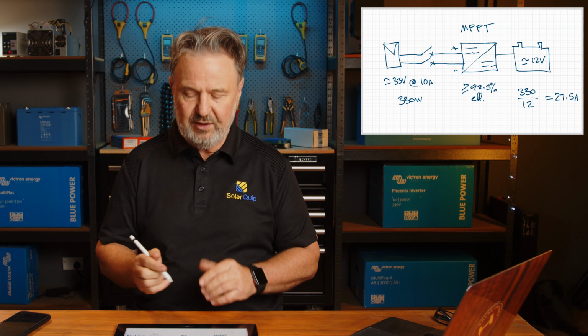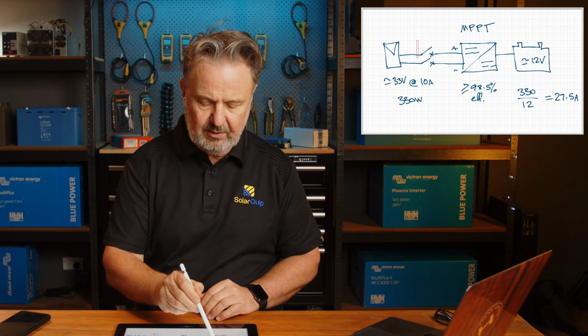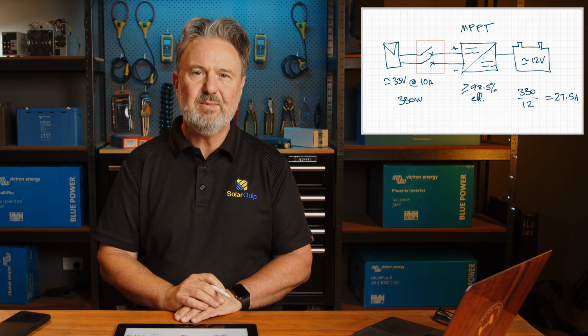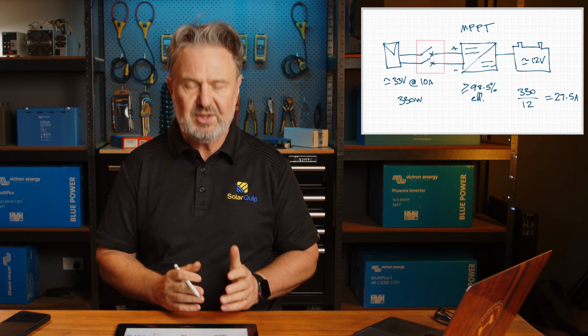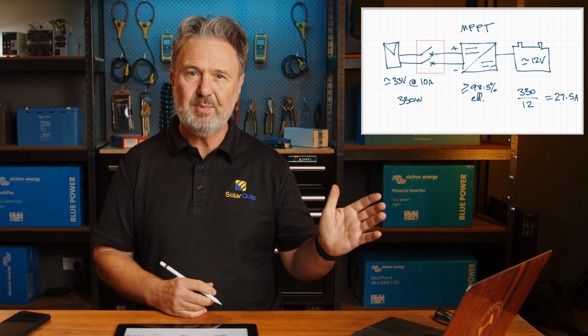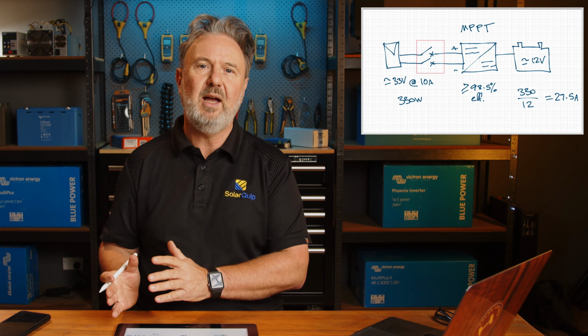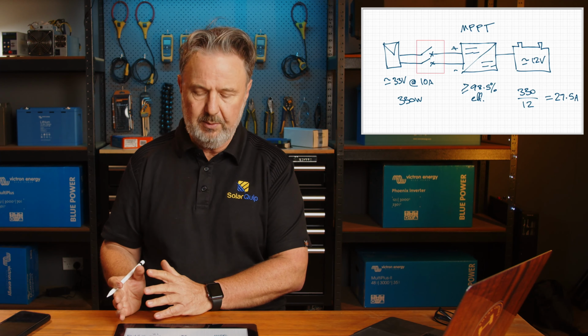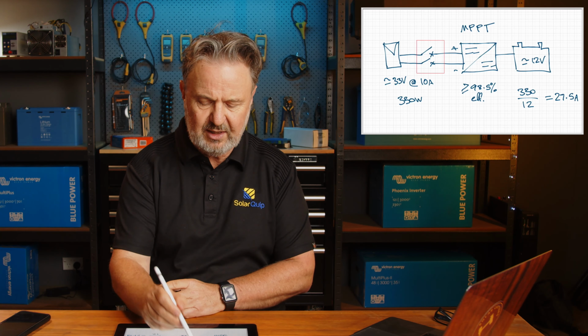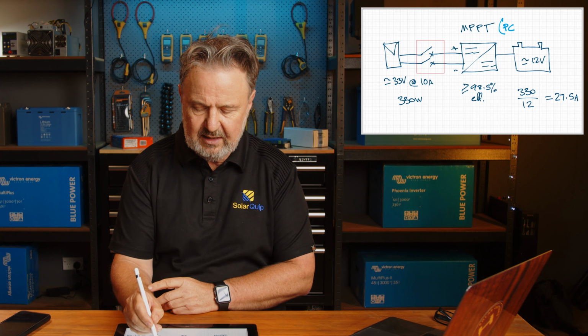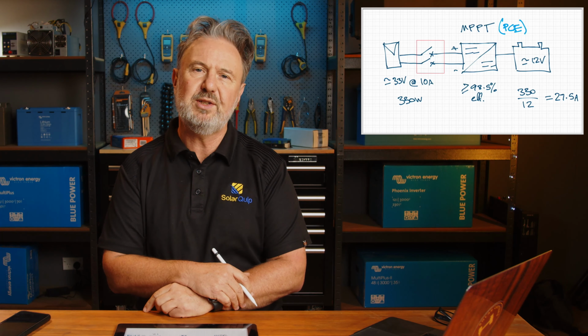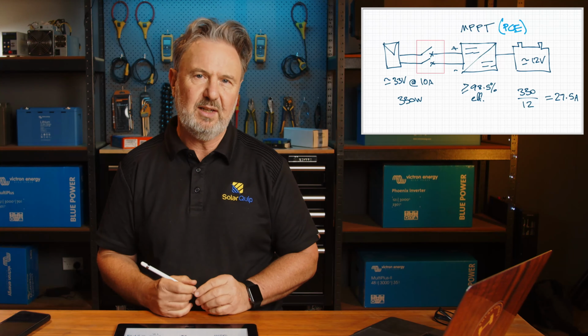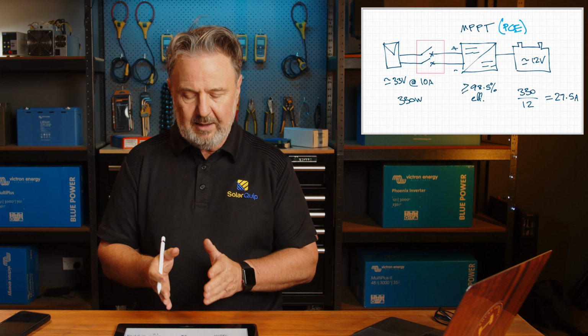Now the requirement, and I'm really focusing on Australian and New Zealand standards here, is that you have galvanic isolation in terms of a switch. Basically it's an air gap switch which disconnects the source, the PV array, from the downstream power conditioning equipment. We often refer to PCE in our standards. Anything that modifies voltage, frequency or current is known as power conditioning equipment. So that PCE needs to be isolated from the PV array.